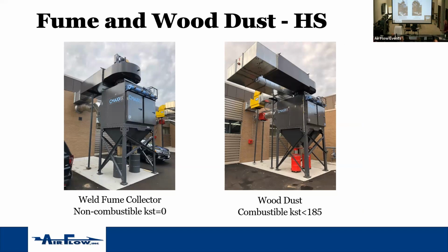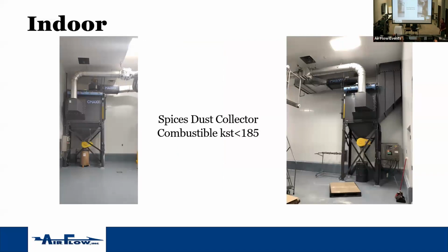On the left, weld fume collector. They're not grinding, they're not doing buffing, they're not doing polishing, just strictly weld fume, no safeties. If you look close enough, you can see this is just that clear vinyl flex we talked about at the bottom, the 2 pipe clamps. No concern about the explosion coming through that. KST is 0.